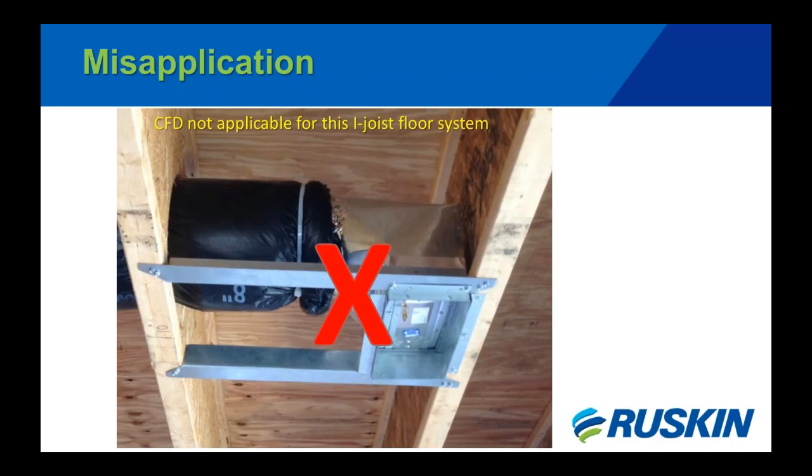Another thing about mechanical engineers: when they're specifying CFDs, if you're specifying a ceiling radiation damper and the roof ceiling or floor ceiling system is noted in the architectural plans, you can obviously check for that design number. You can see if it has a damper associated with it or not. Usually this is going to help solve a lot of problems up front. The more information, the more that can be figured out up front about the application, which damper type, or maybe there's no damper type and you may have to build a rated shaft. Any initial understanding of the design numbers that are specified is only going to help matters. So we would always promote that practice.